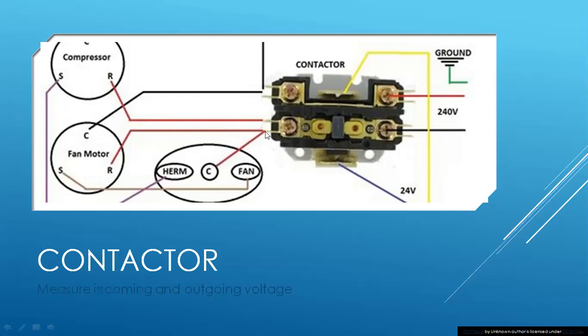So it is imperative, in a case like that, if you get lock rotor amps, come back, check your capacitor, make sure it's good. The next thing you want to do is check your wiring. Because if you cross, for instance, your red and your black here to your compressor, it will give you what appears to be lock rotor amps. It'll keep doing that. Just by switching these two, or ensuring that your common is on the capacitor properly.